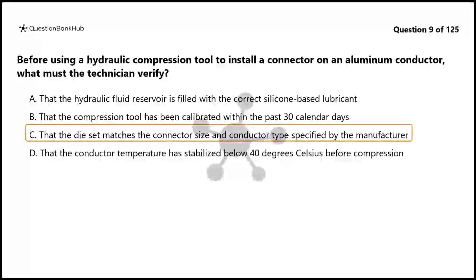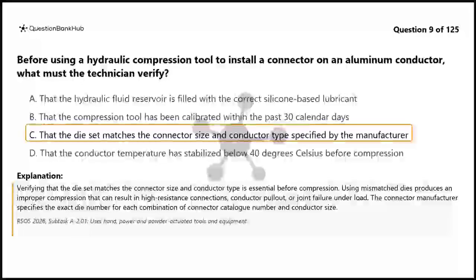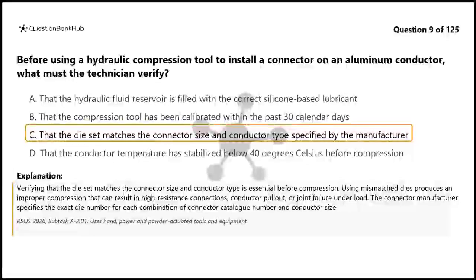The correct answer is C. Verifying that the die set matches the connector size and conductor type is essential before compression. Using mismatched dies produces an improper compression that can result in high-resistance connections, conductor pullout, or joint failure under load. The connector manufacturer specifies the exact die number for each combination of connector catalog number and conductor size.